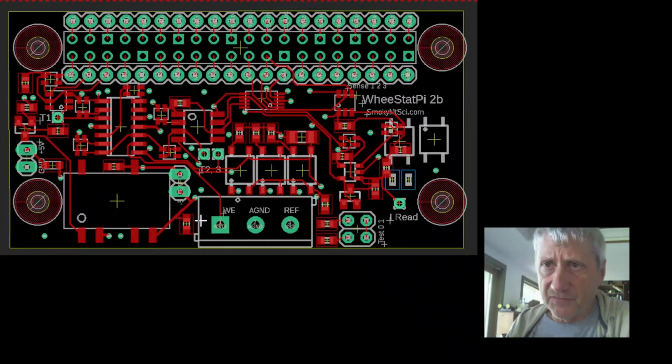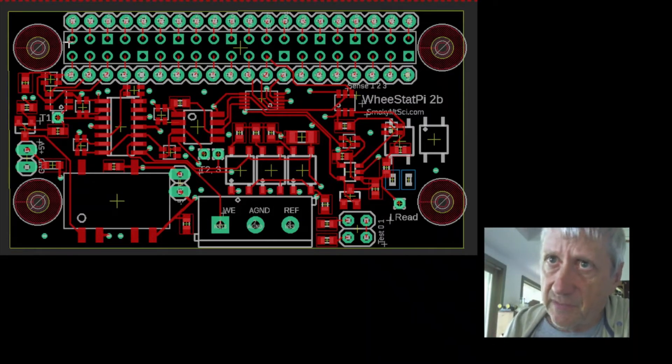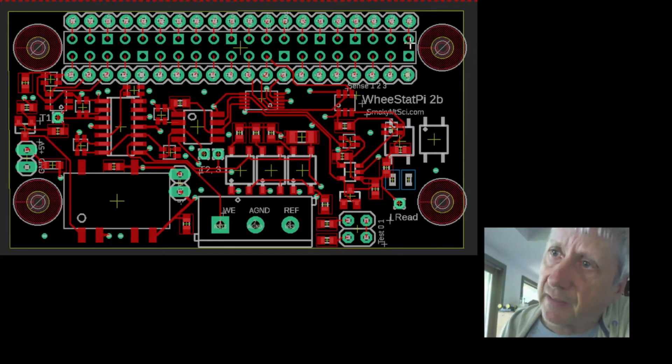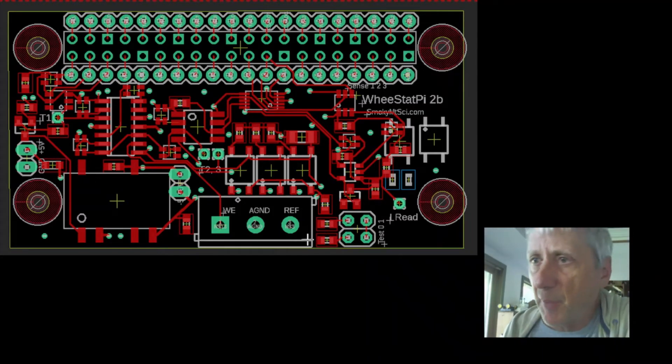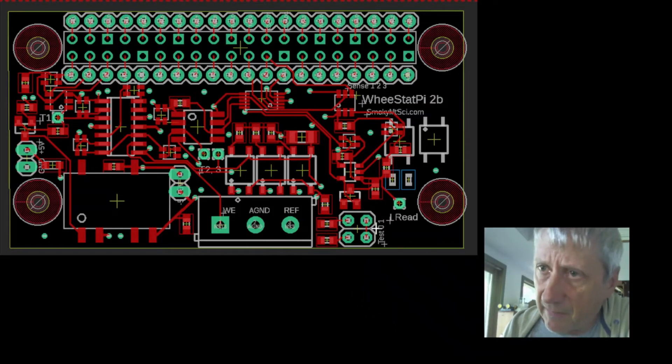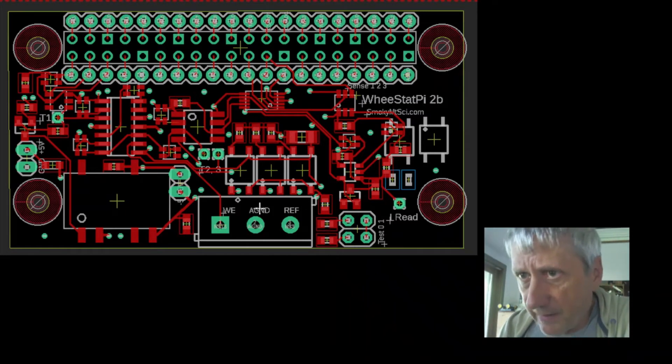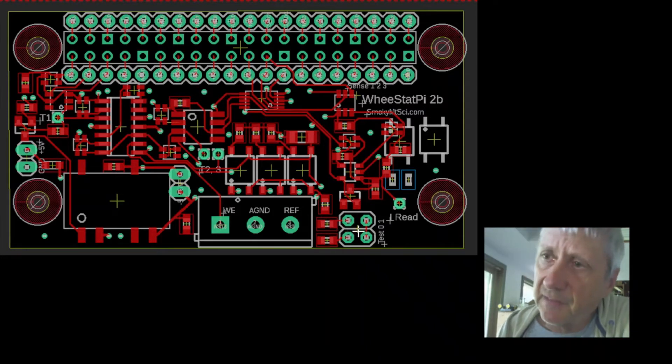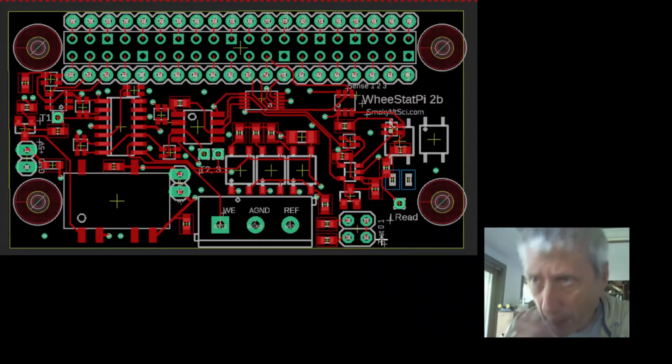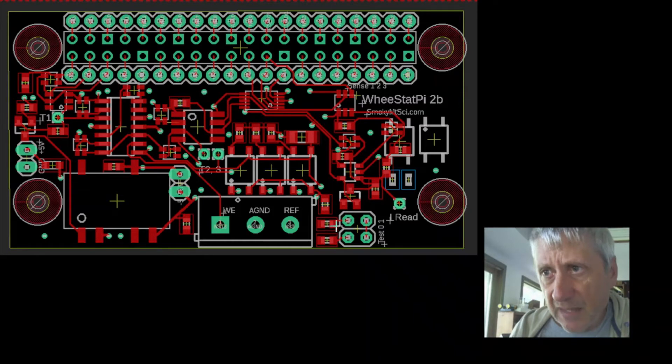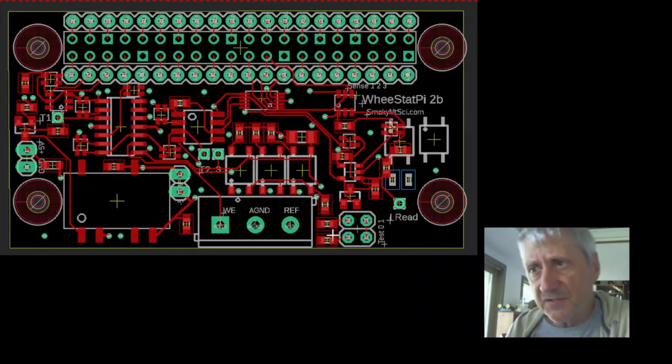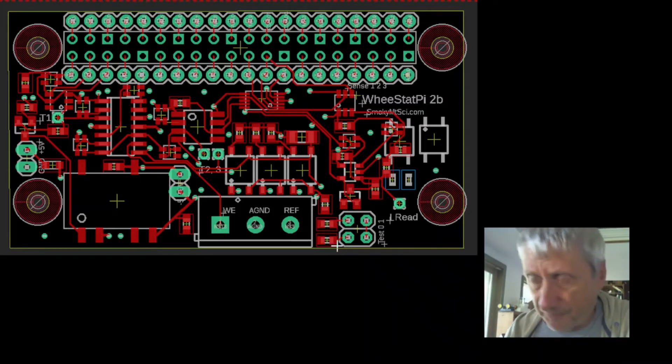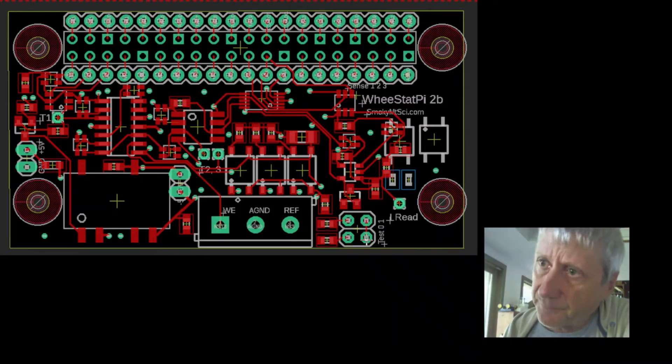You should probably tell me what you want to have in terms of lengths of the wires and the connectors that are required to connect to the apparatus. The other thing I want to show you, this is a top view of the board. There's where the connector to the Raspberry Pi is. Down here, just to the lower right of the terminal block, there's something that says test 01 on the board, and there are two test resistors built into the instrument.